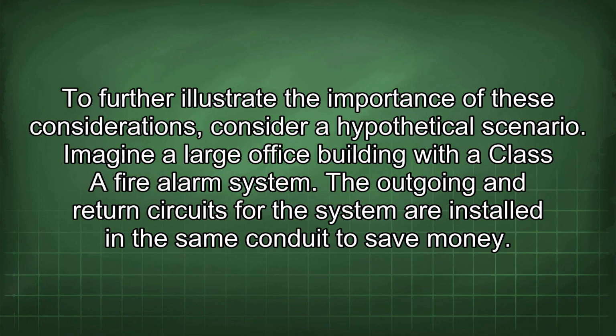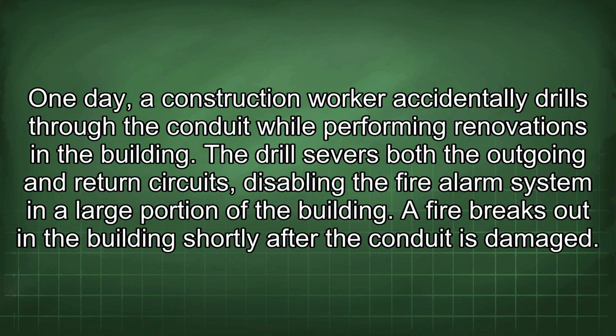To further illustrate the importance of these considerations, consider a hypothetical scenario. Imagine a large office building with a Class A fire alarm system. The outgoing and return circuits for the system are installed in the same conduit to save money. One day, a construction worker accidentally drills through the conduit while performing renovations in the building. The drill severs both the outgoing and return circuits, disabling the fire alarm system in a large portion of the building. A fire breaks out in the building shortly after the conduit is damaged.